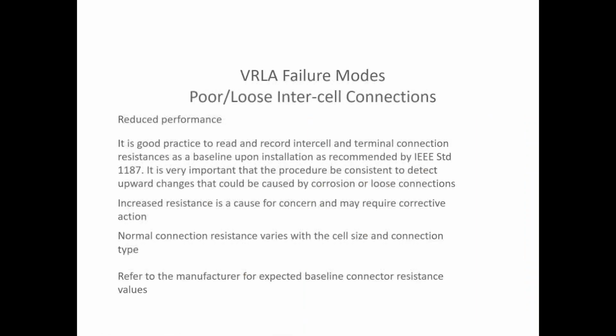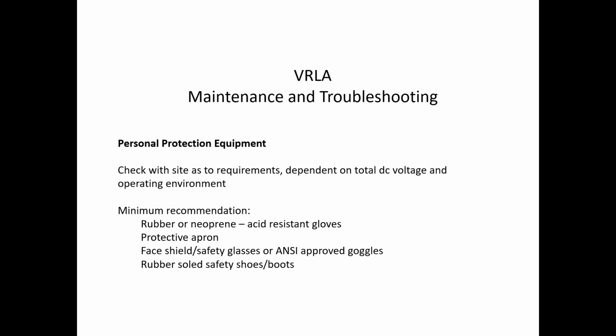So again, typically once you take care of it from the initial install, you're okay, but that's, like I said, something to keep in mind. So good practice. I'm not going to read through all of the slides, but the connection resistances can vary depending on the length, the span of the connection. Usually they're uniform within the string, but occasionally you'll have a cable that'll jump stack to stack. Obviously those will be higher. You go back to the manufacturer, they'll give you the recommendation on what those resistance readings should be.